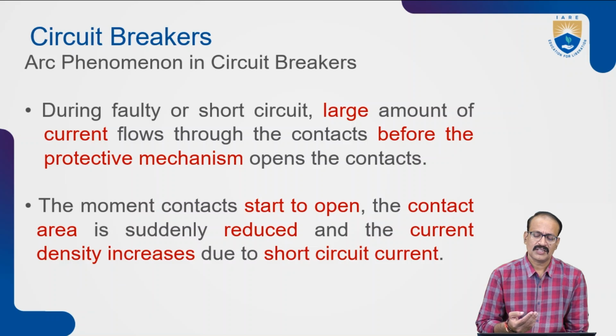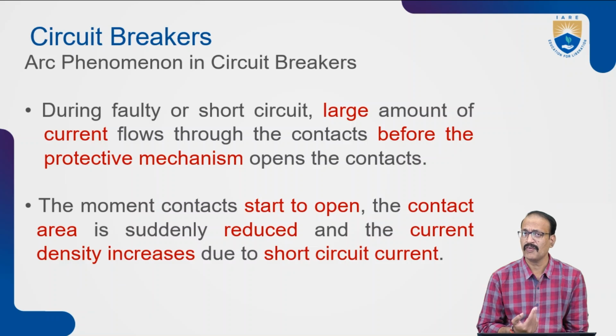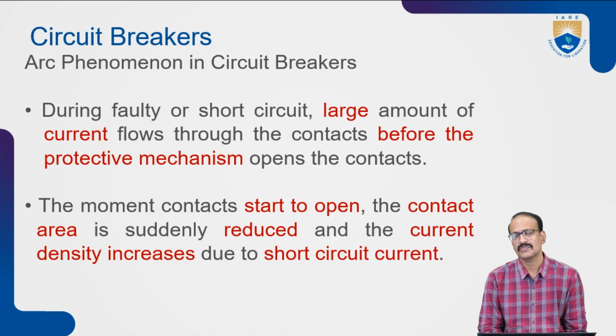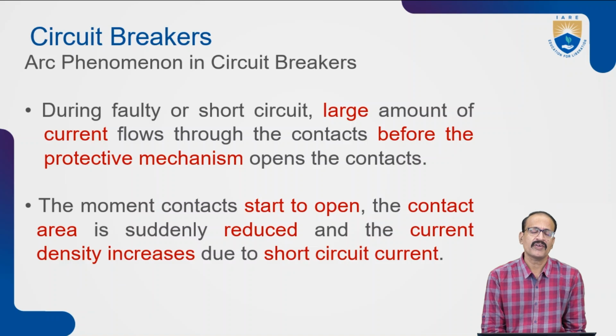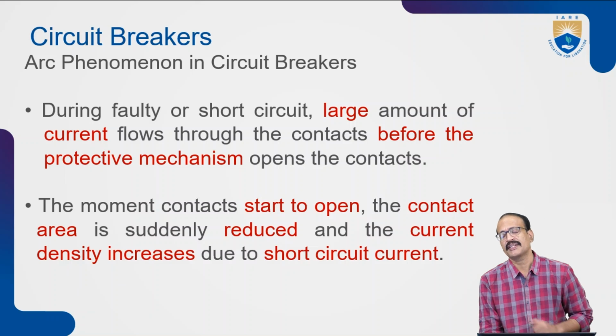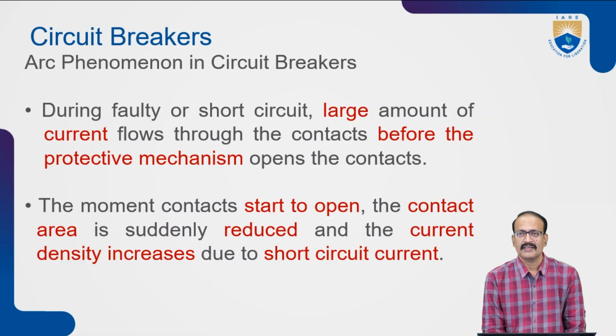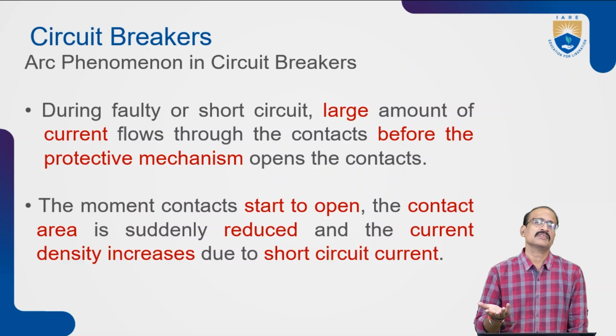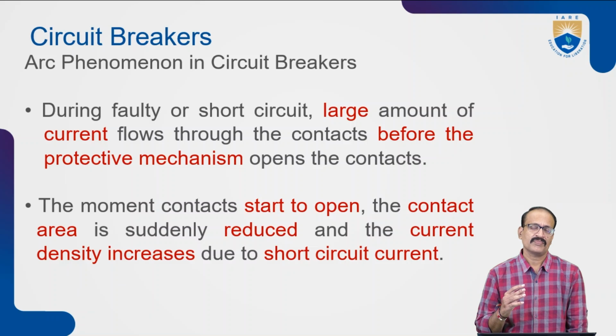Okay, so the current is flowing normally and suddenly a fault or short circuit occurs. That means more current is passing. It has already happened before the protective system gets activated. Before the protective system gets activated, a large amount of current has already passed through these contacts. If it had not passed, there would be no question of striking the arc. So before the protection system gets activated, a large amount of short circuit or fault current already passes through these contacts.